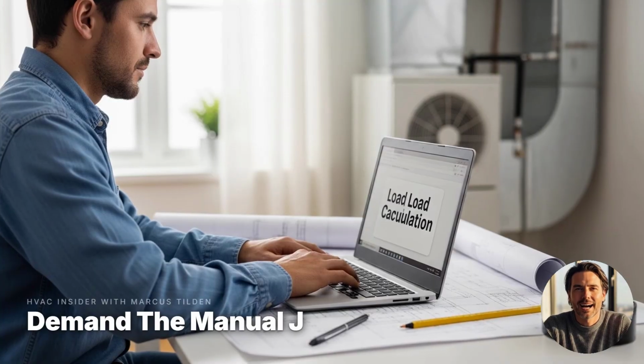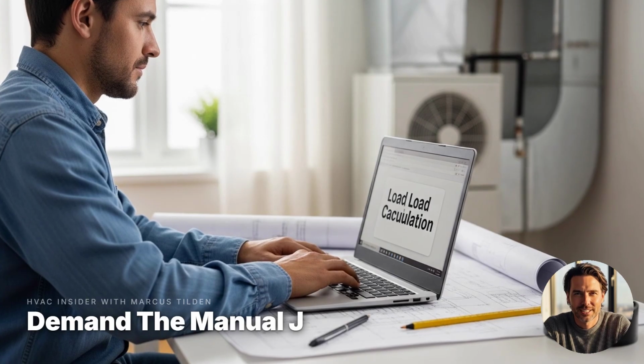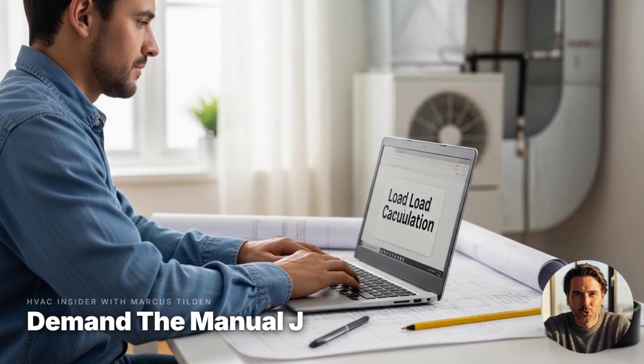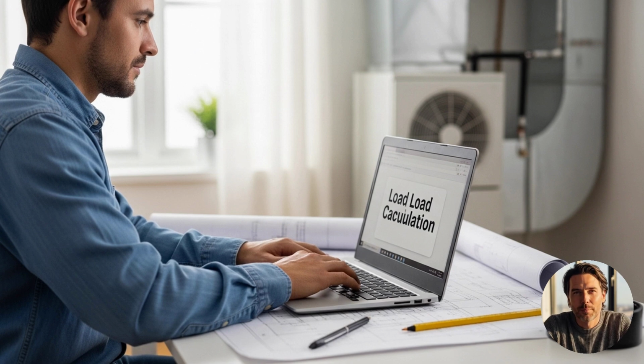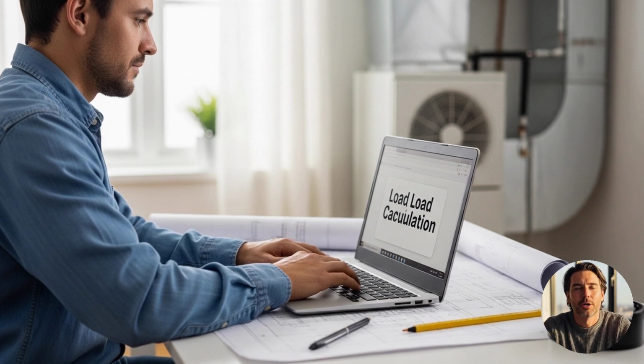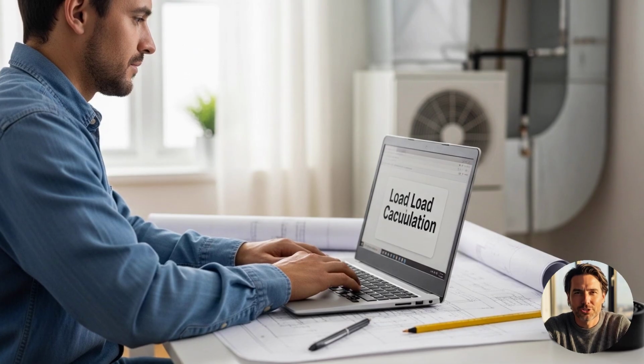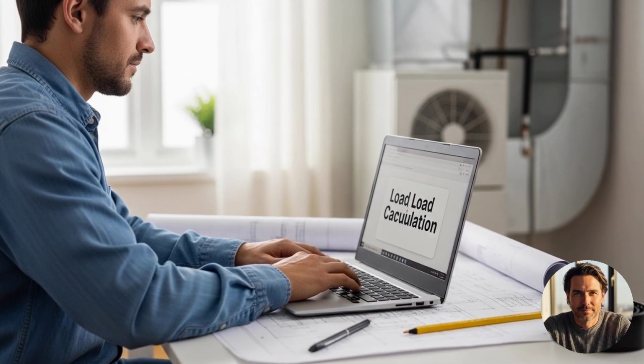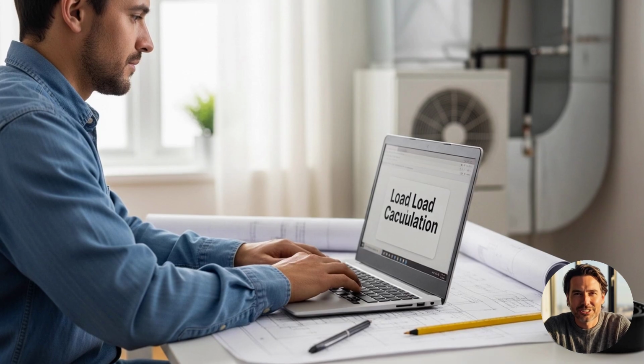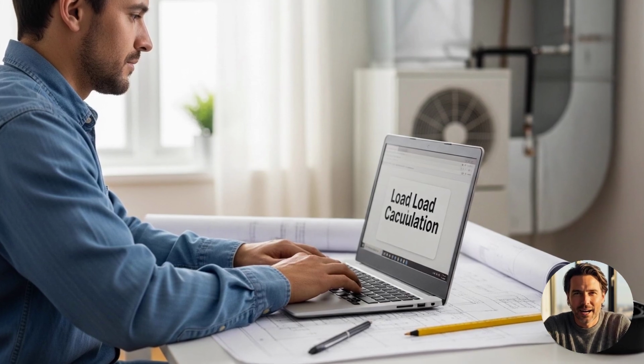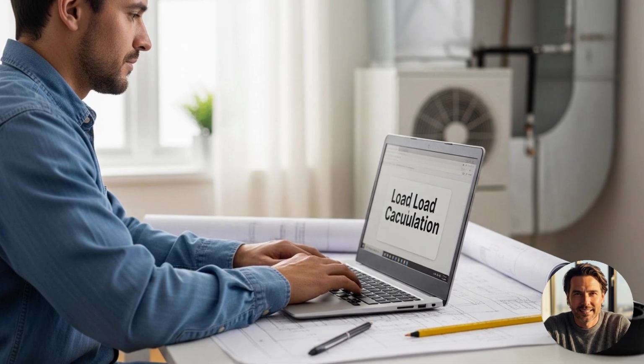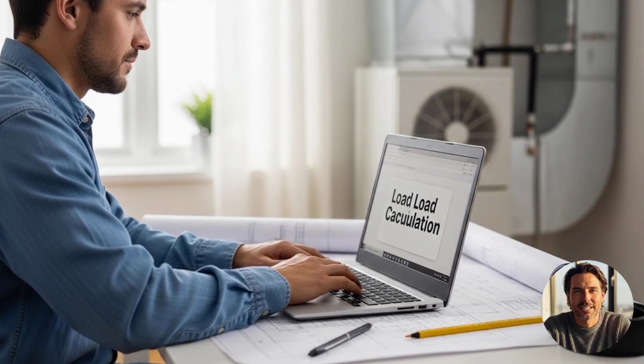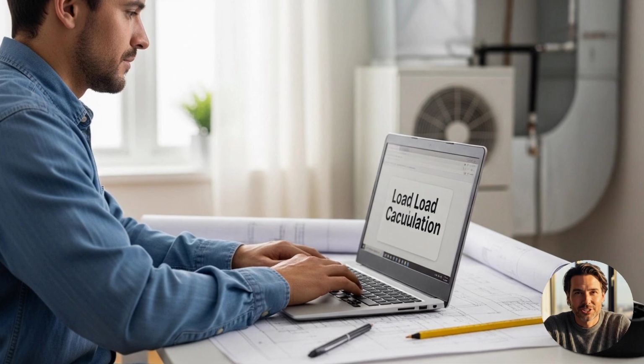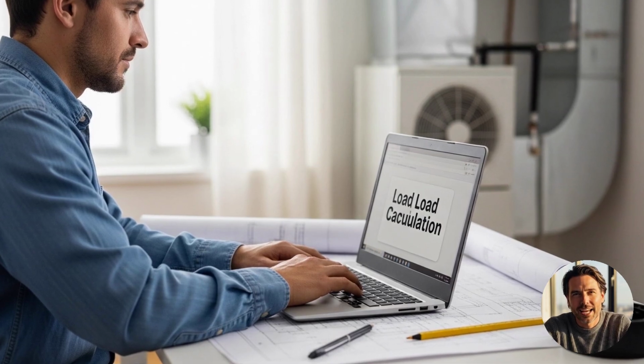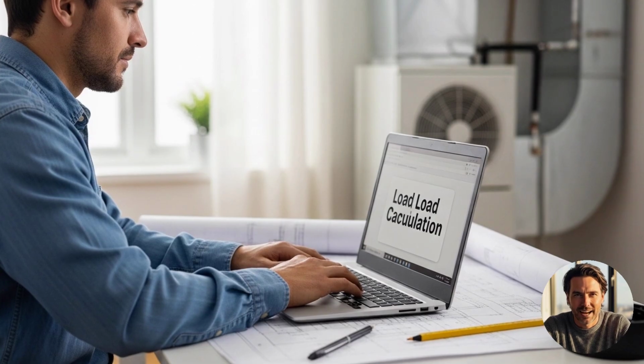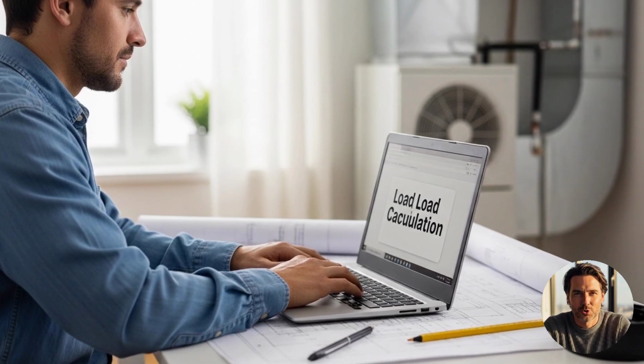So how do you know the size is right? There is an actual calculation for it called a Manual J load calculation. It measures your home's heat loss and heat gain using your square footage, your windows, your insulation, your climate. A contractor who sizes your system by rule of thumb, or by just matching the old unit, is guessing with your money. This is not complicated, it was just never explained to you. Ask for the Manual J in writing. If they refuse or laugh it off, that tells you exactly who you are dealing with.